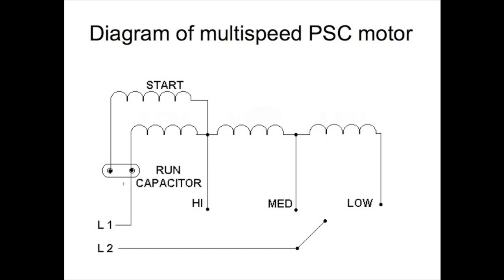You can do that, but the reason they don't always do that with these PSC motors they use as fan motors is they'll go too slow. When they want speeds on these fan motors, they want kind of a minimum speed, not half speed.